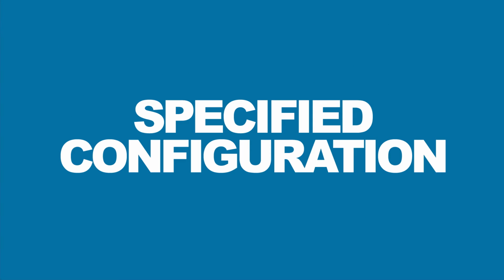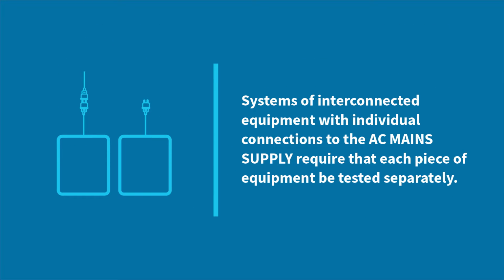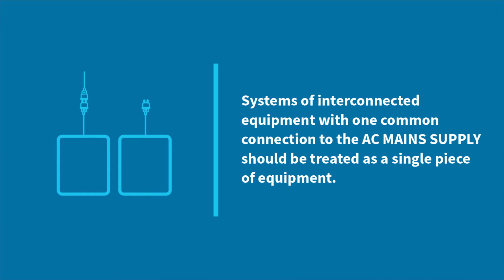Specified configuration. Systems of interconnected equipment with individual connections to the AC mains supply require that each piece of equipment be tested separately. Systems of interconnected equipment with one common connection to the AC mains supply should be treated as a single piece of equipment.